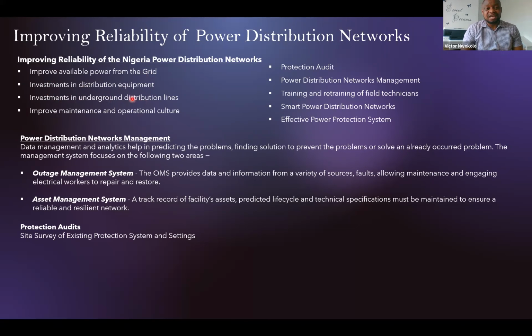This will improve a lot of power reliability, because most of the faults we get on overhead system can be eliminated through underground distribution. So improve maintenance and operating culture. We need to look at improving the way we maintain our distribution equipment. In Nigeria, I can see in many feeder pillars, instead of a suitably rated fuse, sometimes they use wires as fuse, which is very bad because one, it has safety implication, and two, it kills the equipment because you're not giving the equipment proper protection.